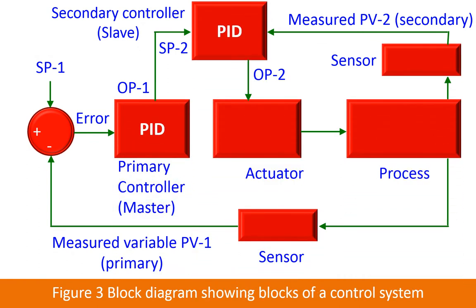The cascade control concept is illustrated in this block diagram. There are two controllers: a primary controller and a secondary controller. The output of the first controller OP1 is used as set point SP2 of the secondary controller. The primary controller is called the master and the secondary controller is called the slave. The slave follows the master.